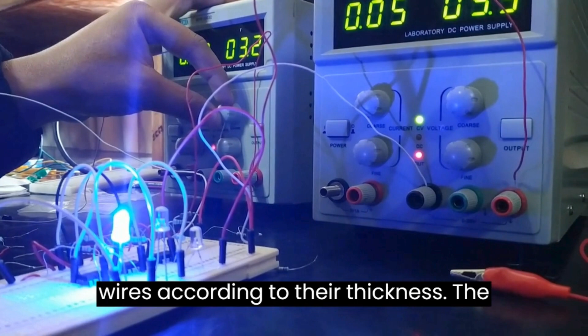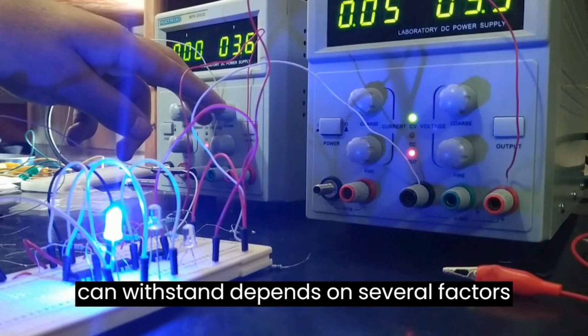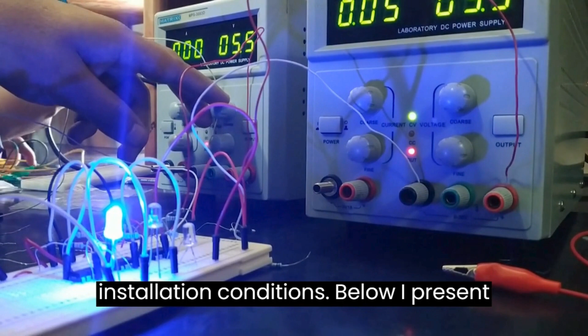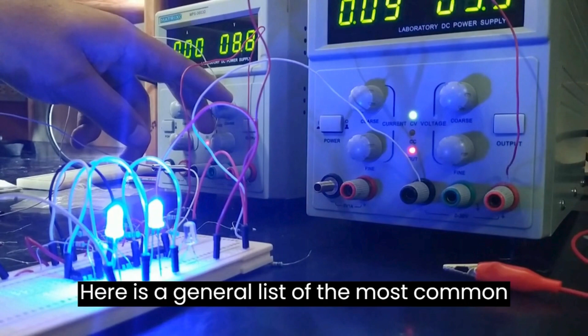Technical characteristics of electrical wires according to their thickness. The electrical current capacity that a wire can withstand depends on several factors, including its thickness, gauge, conductive material, insulation, and installation conditions. Below, I present a general relationship between wire thickness, gauge, and supported current capacity for wires commonly used in residential electrical installations.